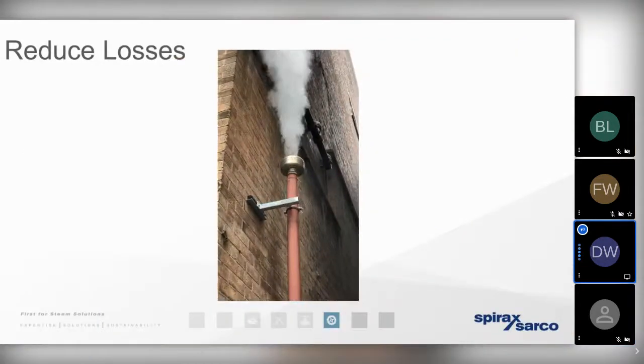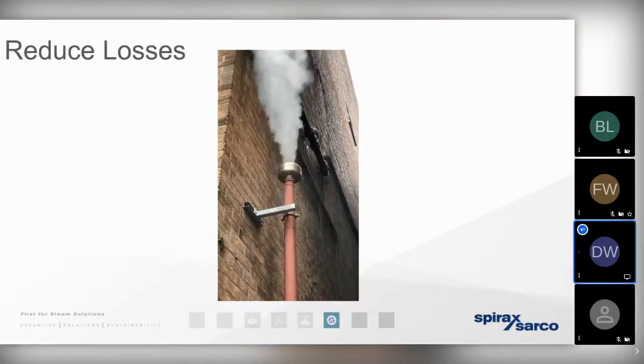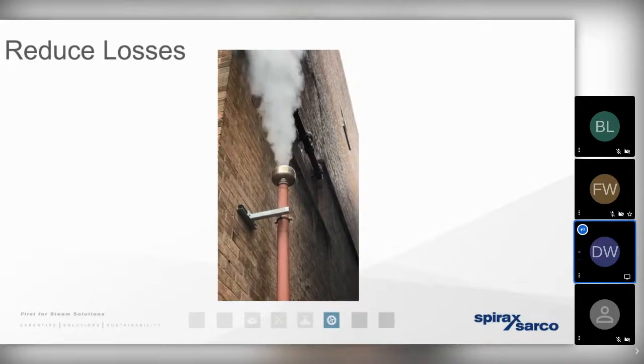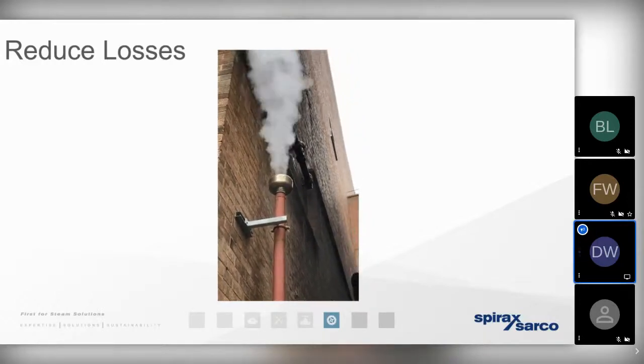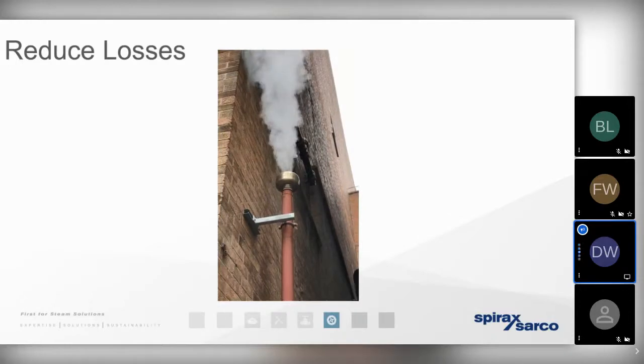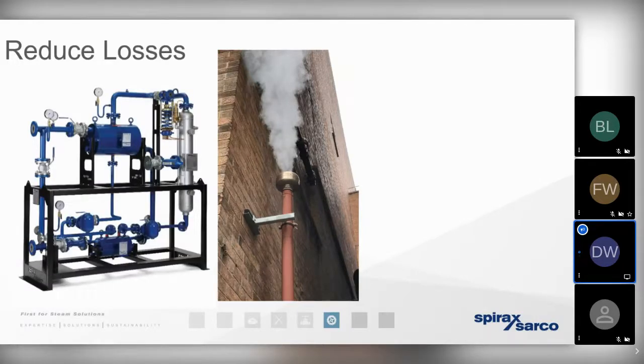So let's look at those steam vents in a little bit more detail. As we've mentioned, that venting steam could be as a result of flash steam, if we've got a significant pressure drop going across a steam trap, or it could be as a result of failed open steam traps. The visual telltale is generally very easy to see, especially on a cold and wet day when that steam has been venting to atmosphere. We just need to think about different ways that we can address that steam that is ultimately being lost. So if we've got a significant load, we can perhaps look at ways that we can put that heat energy into another heat sink.